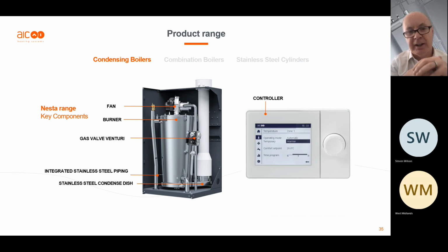Okay, and if you look internally at the heat exchanger there, there are no mechanical joints on that heat exchanger. Everything is welded stainless steel. So the weakest part, the mechanical joint, is not there. Also, if you look at the bottom of the heat exchanger, the condense dish is also manufactured in welded stainless steel, so there's no threat of any perforation to washers going around that, so you're not going to get any products of combustion escaping into the casing of the boiler either.